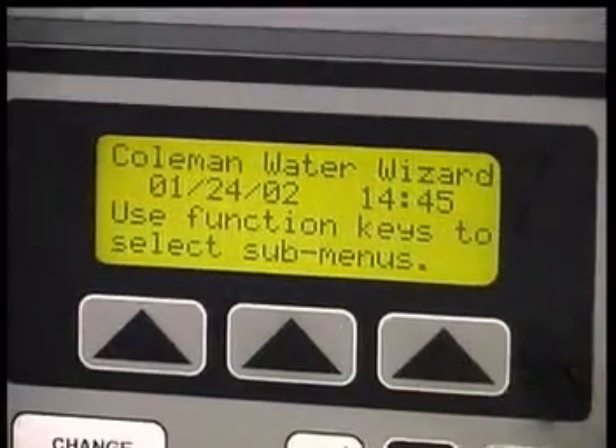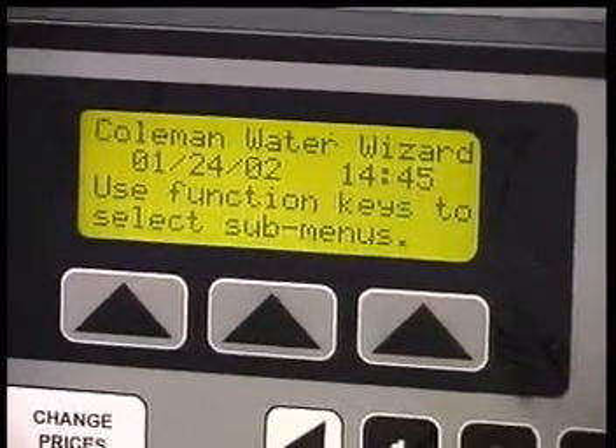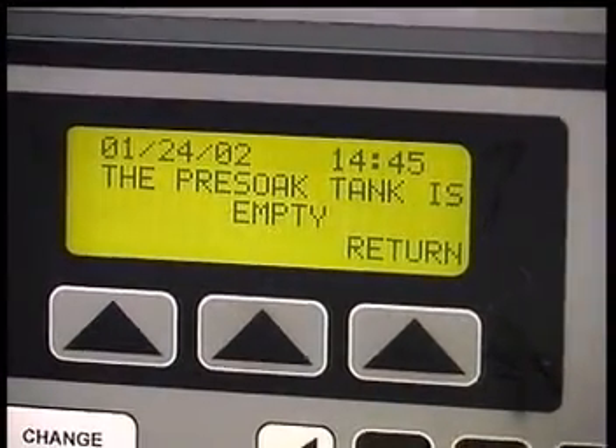Each chemical delivery pump is protected by an electronic float switch located in the chemical mixing tank. If the tank level is allowed to drop below the float switch, the system will disable that pump, send an error message to the electrical control panel which will display the message on the operator interface screen, and print it out if optional printer is installed.